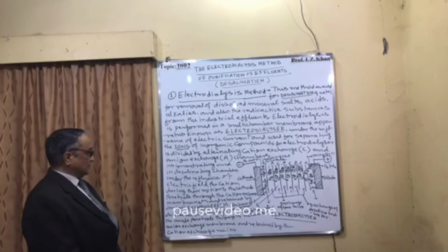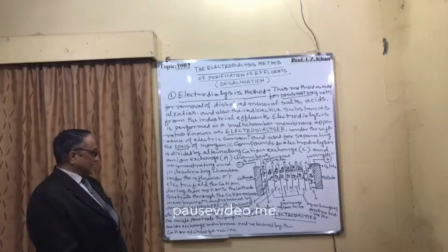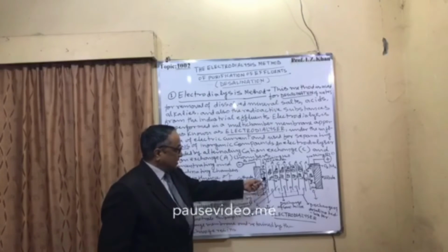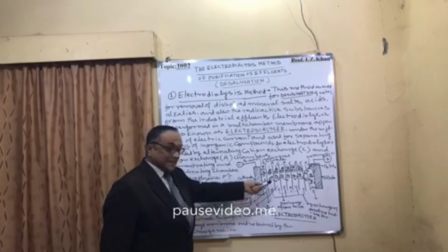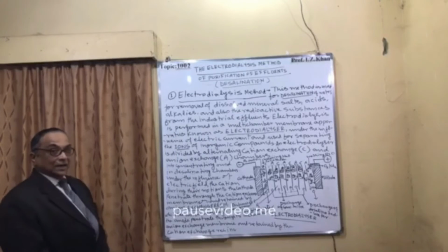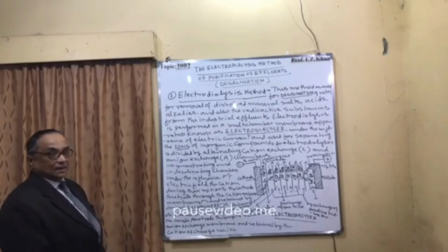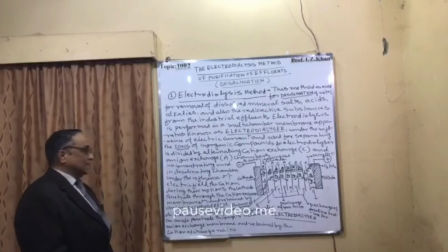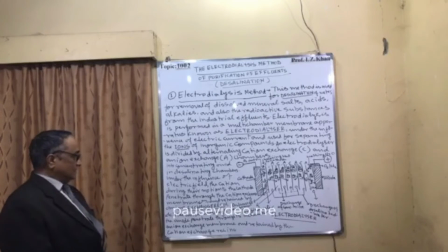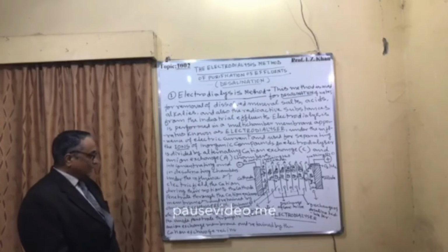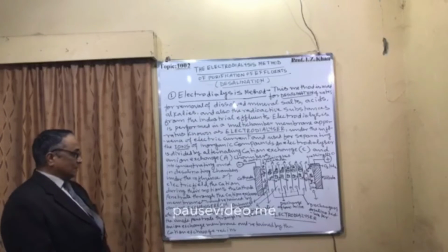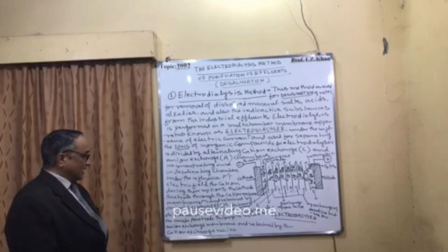Under the influence of the electric field, the cations during their motion to the cathode penetrate through the cation exchange membranes and are retained by anion exchangers. So the cation exchange moving and retained by anion means positive and negative, so they are exchanging with each other. In this way, with this exchange through the membrane of those chambers, they are gaining or losing electrons, and are converted into atomic and molecular state by this exchange resin. While the anions moving to the anode penetrate through the anion exchange membrane and are retained by the cation exchange resin.